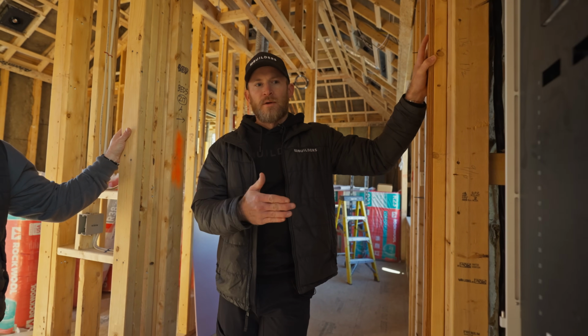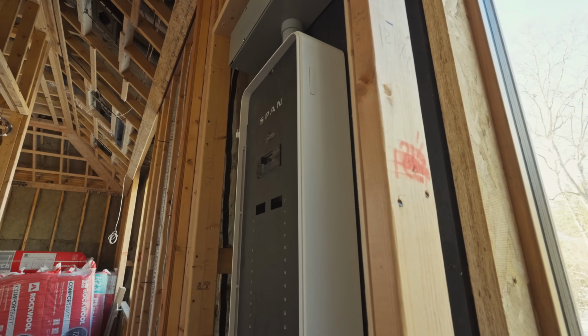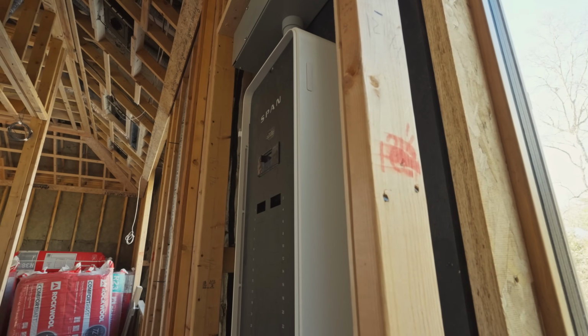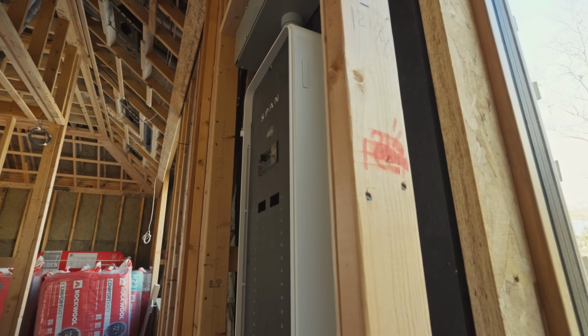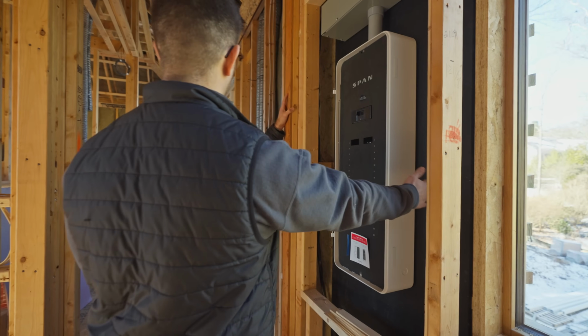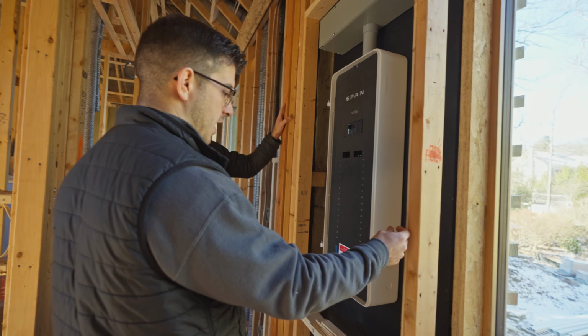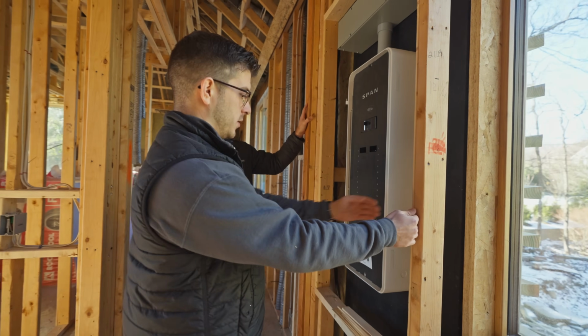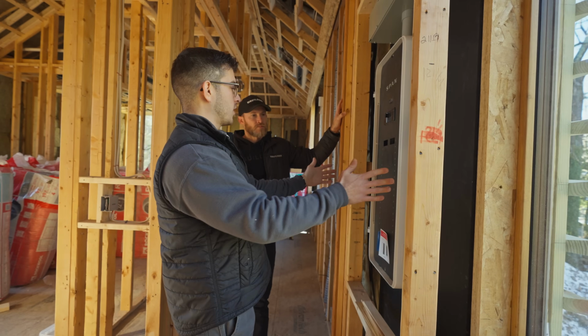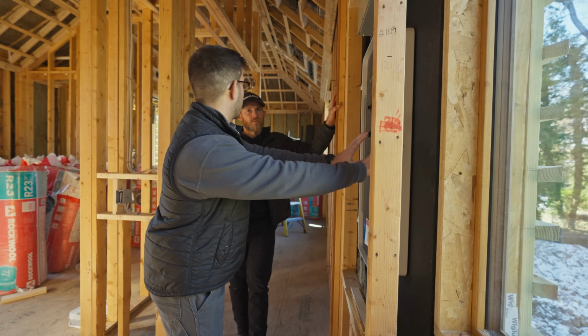How are we getting away with that, knowing we have clearance issues? We worked with the local inspector and saw what he was requiring. Generally the panel can't be recessed into the wall, so we're actually set back about a half inch in the rough framing. But where this panel opens up, the panel's right in front of you, you're not reaching into a cabinet.